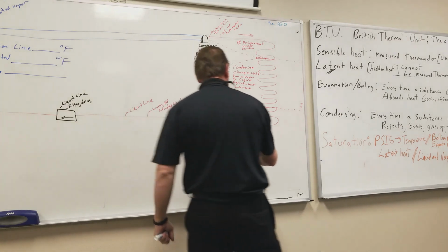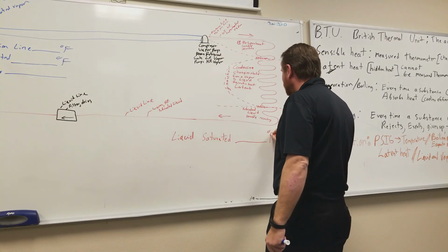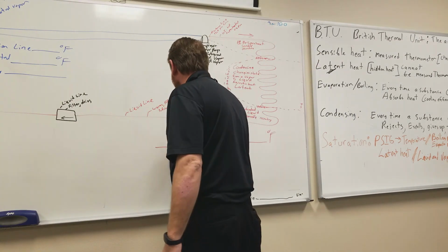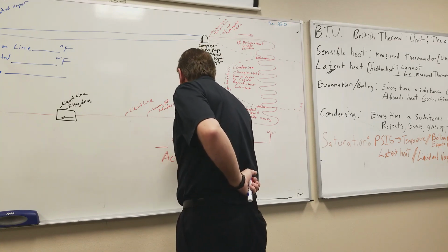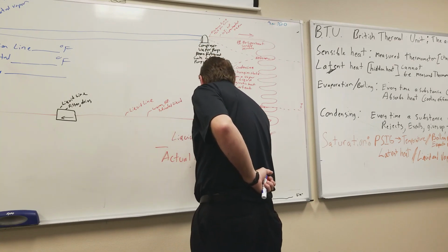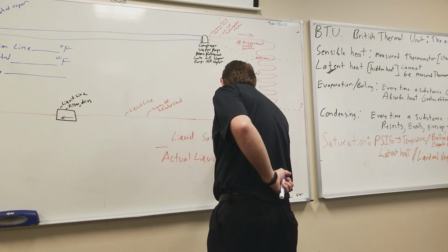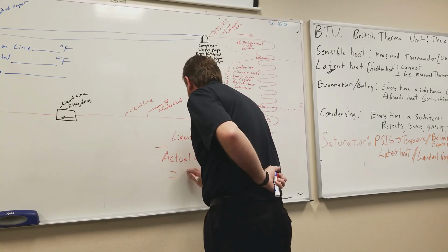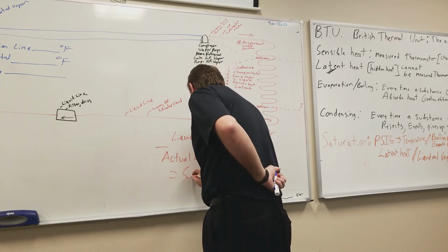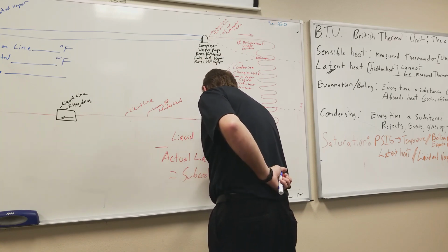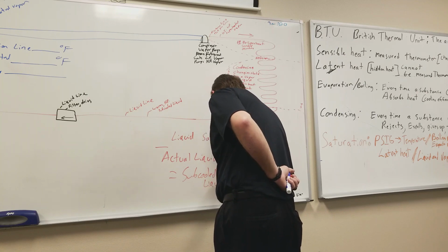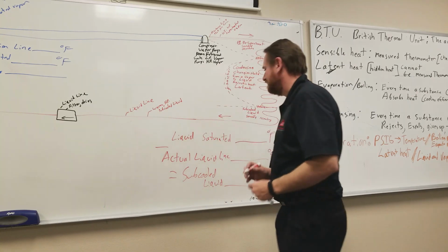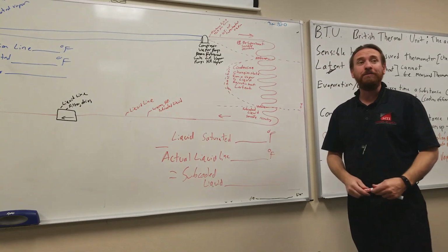Liquid saturated temperature minus the actual liquid line temperature equals subcooled temperature. Subcooled liquid. It's a warm subcooled liquid.